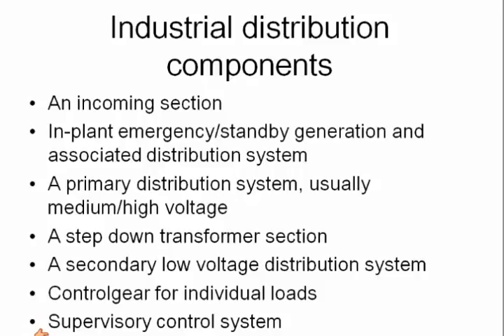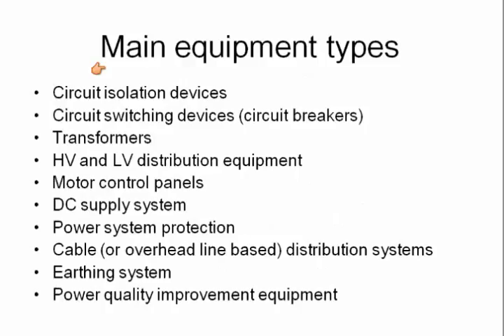Main equipment types include circuit isolation devices, circuit switching devices, transformers, HV and LV distribution equipment, motor control panels, DC supply system. Why do you need a DC supply system? What's the key benefit of having a DC supply system? The key benefit is to provide power for your protection relays, circuit breaker tripping and closing, your control panel equipment, indication lamps and alarm systems, as well as your control system.